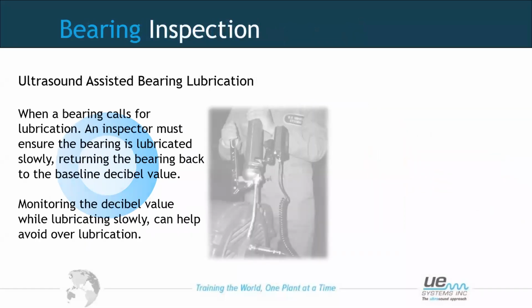So when we apply the grease while we're listening, we want to apply grease slowly and consistently, listening for a drop in decibel value. If we see a drop in decibel value, that tells us we're reducing the friction within the bearing. As we continue to lubricate and the sound continues to go down, we understand what the bearing needs. Once the decibel value does not drop any further, that's the bearing telling us that there is no more grease required and it has enough.